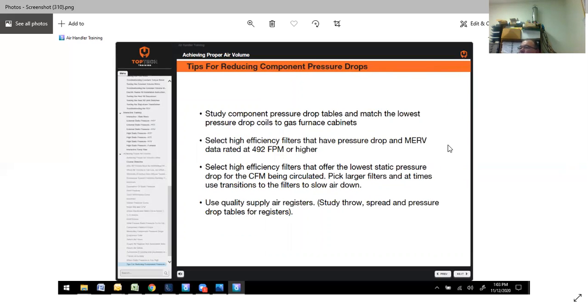Tips for reducing component pressure drops. Study component pressure drop tables. Match the lowest pressure drop coils to the gas furnace cabinets. Select high efficiency filters that have pressure drops and MERV ratings rated at 492 feet per minute or higher. Select filters that offer the lowest static pressure drops for the CFM being chosen. Pick larger filters, 4-inch, 5-inch, and use transitions to the filters to slow air down.